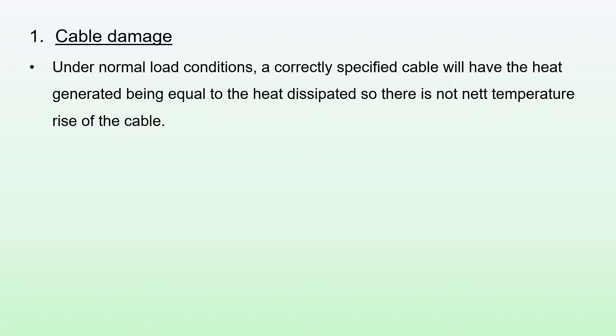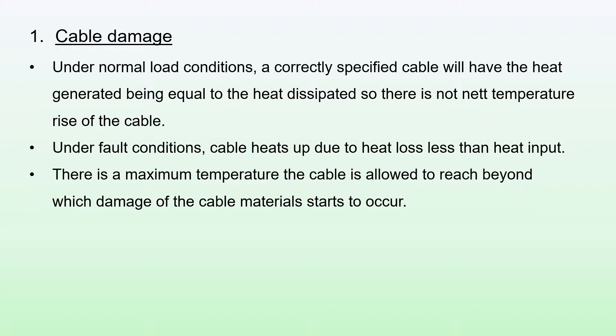Under normal load conditions, a correctly specified cable will have the heat generated being equal to the heat dissipated, so there is no net temperature rise of the cable. Under fault conditions though, the cable heats up due to heat loss being less than the heat input, with heat input being directly proportional to the large fault current flowing. There is a maximum temperature the cable is allowed to reach beyond which damage of the cable materials starts to occur. For XLPE and EPR cables this temperature limit is 250 degrees. For PVC insulated cables the temperature limit is 160 degrees.